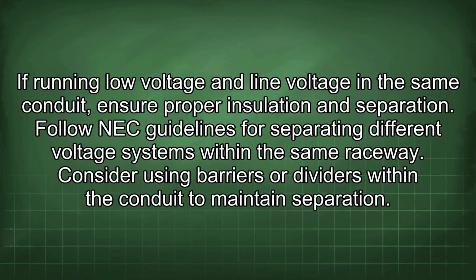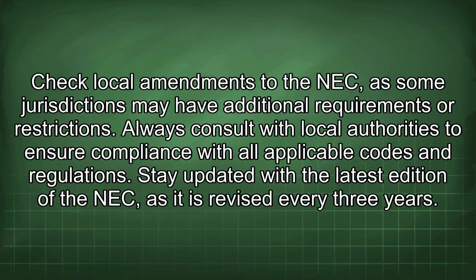If running low voltage and line voltage in the same conduit, ensure proper insulation and separation. Follow NEC guidelines for separating different voltage systems within the same raceway. Consider using barriers or dividers within the conduit to maintain separation. Check local amendments to the NEC, as some jurisdictions may have additional requirements or restrictions. Always consult with local authorities to ensure compliance with all applicable codes and regulations.